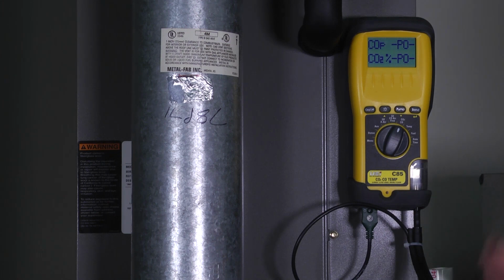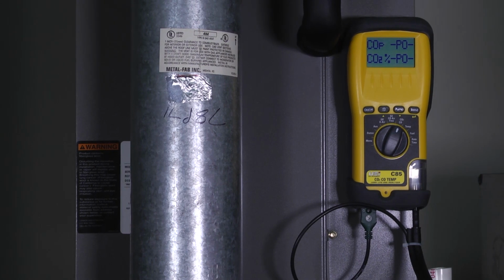Our flue gas analyzer is going to tell us how much CO the unit's producing, how much excess air the unit's got, and what the temperature of the flue gases is going out of it. And you look at me and go, Mark, that's great, but what do I care? We take a look at a gas furnace and you say to me, Mark, a gas furnace burns pretty cleanly. That is true, but there are times when a gas furnace can produce carbon.